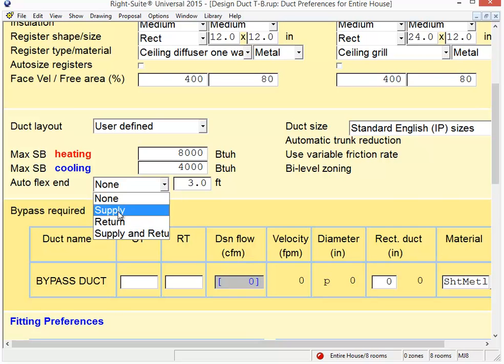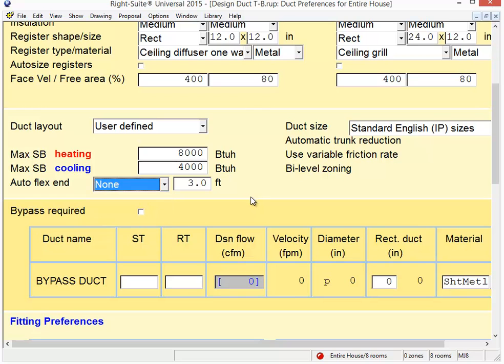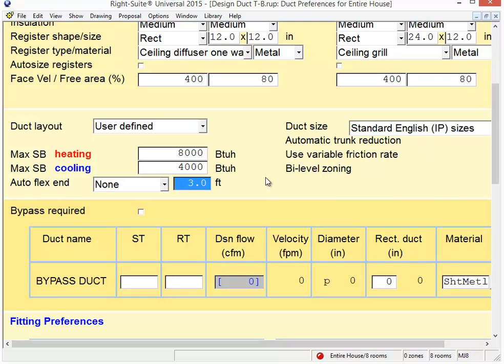I'm going to do just the supply side for my flex ends. But before I do that, I'm going to set an actual distance that I would like the flex ends to use. It's important to do it in this order if you're going to do it after the fact like I am because it really is a single time application. Otherwise, I might have to redraw some of the duct work because the program does have to divide the ducts into multiple pieces.